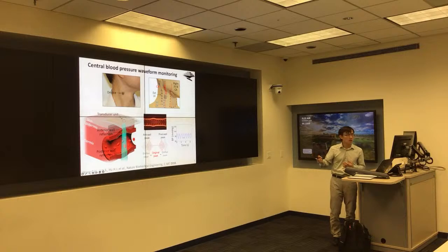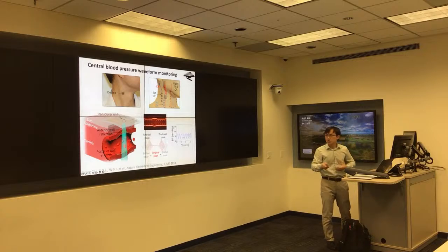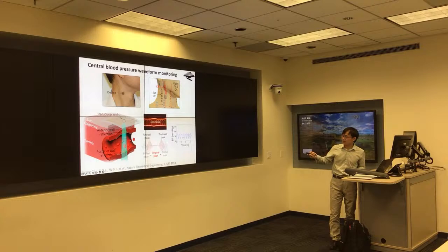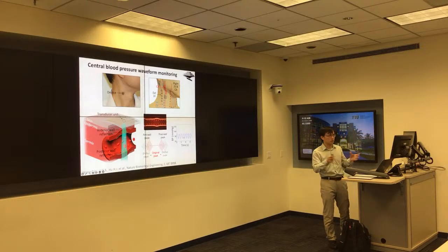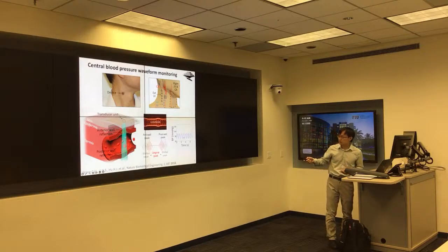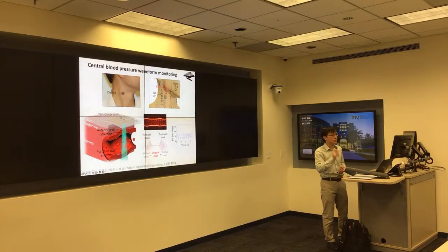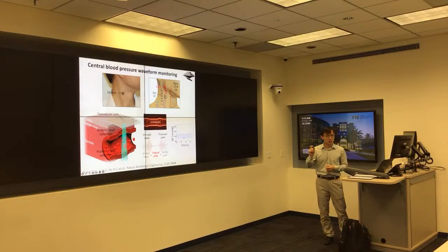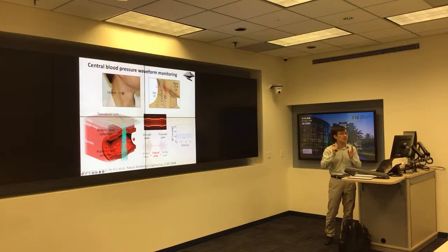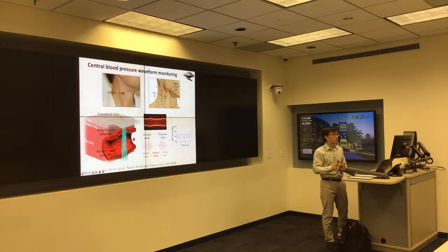And as you can imagine, when this blood pressure pulse comes in, your vessel will actually dilate, collapse, right? And then that means what? That means those two peaks will shift back and forth during this vessel pulsation. And by monitoring the distance between those two peaks, you are measuring vessel diameter. And through a series of well-established equations and calibration, you can convert vessel diameter to blood pressure. Basically, the higher the blood pressure, the larger the vessel diameter.